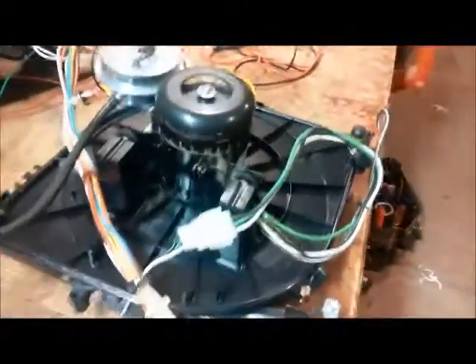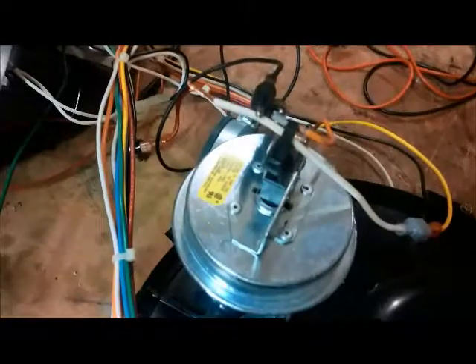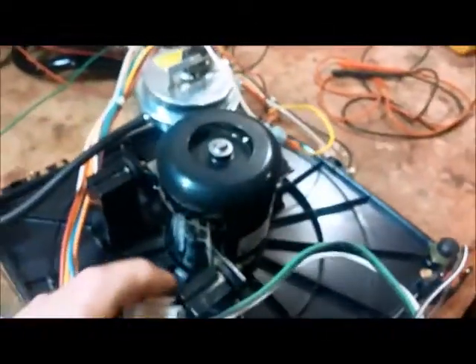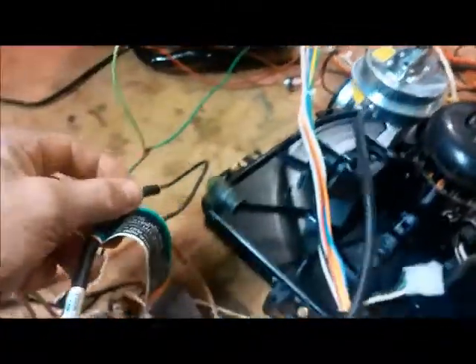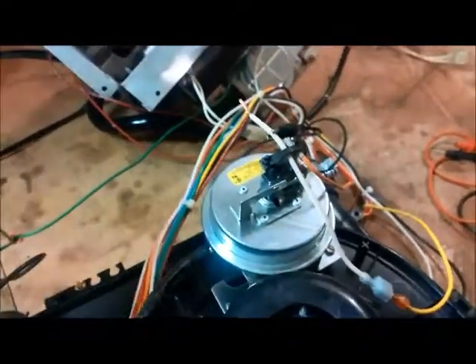The next thing that happens is the pressure switch should close. Right now we don't have our pressure switch hooked up, and this motor is making an awful lot of noise. But let's just disconnect the inducer motor for the sake of this, because our pressure tubing, which would be hooked on from the pressure switch to the collector box or whatever's going to draw to close our pressure switch, is not hooked up.